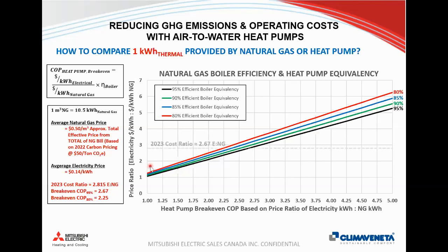So on this chart, you basically draw a horizontal line on the y-axis here for the price ratio, and wherever it intersects with whatever boiler efficiency you're comparing it to, you draw a line down, and that tells you the break-even COP. So if we're comparing this to a 95% efficient boiler, we would need a COP of 2.67. If we're comparing it to an 80% boiler, the break-even COP that we need is about 2.25. And again, this doesn't only apply to hydronic heat pumps. This applies to furnaces. This is just a pure energy comparison based off the costs. So it's really useful when you're just looking for a quick rule of thumb to figure out if a particular heat pump application makes sense.